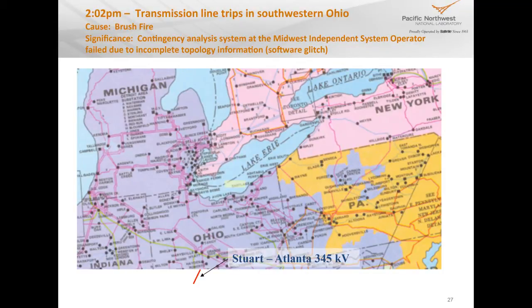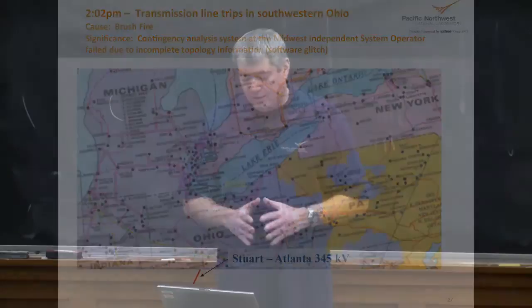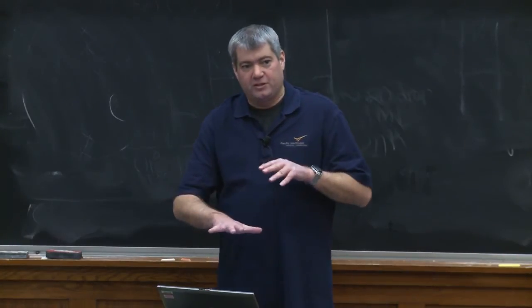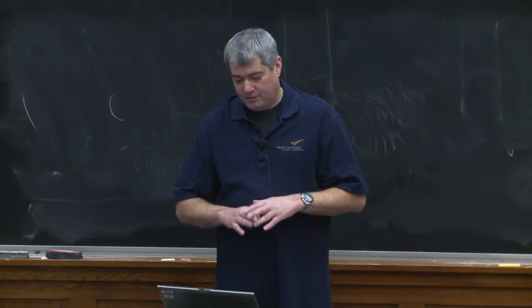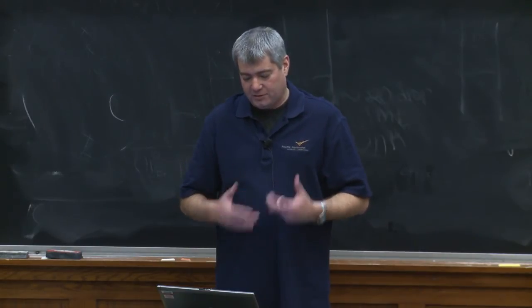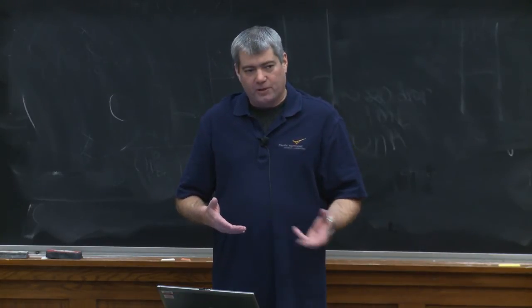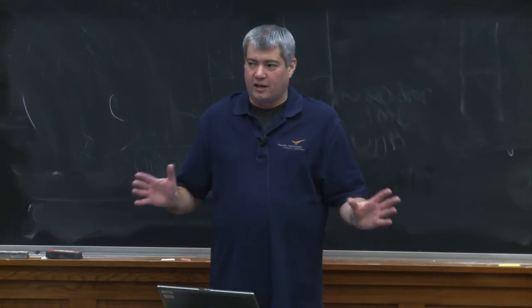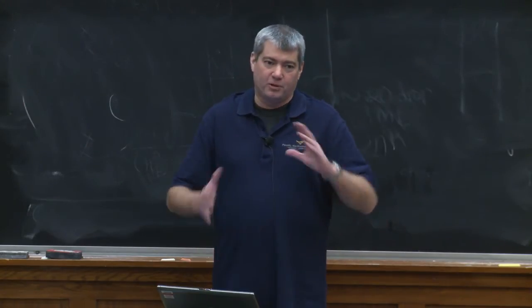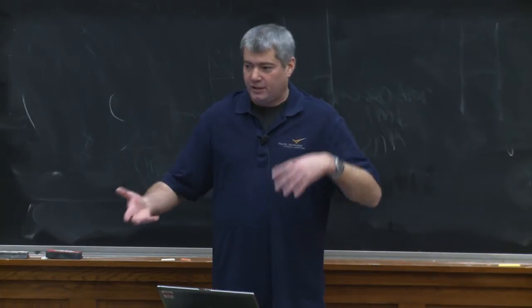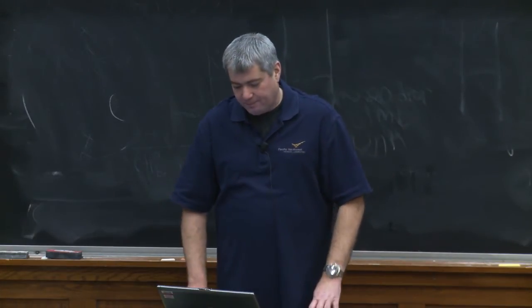Second thing that happened, just off my map here on the bottom of the map, is a line tripped off. This wasn't interesting from an electrical standpoint, but what it did do is it screwed up the computer model called the contingency analysis. It's driven by the state estimator at the Midwest ISO, Independent System Operator. And they're the organization that oversees the First Energy utility company. So they weren't getting good information because of this line that tripped. The problem was the telemetry wasn't correct. They thought the line was in service when the line was really out of service. The computer model didn't match the rest of the telemetry, and tracking down that process took a while.